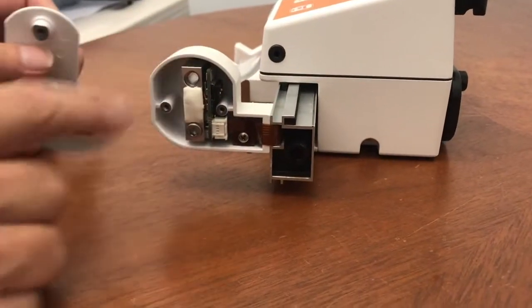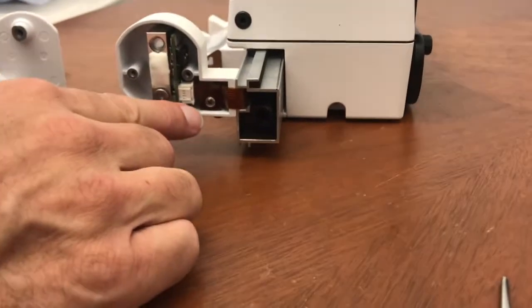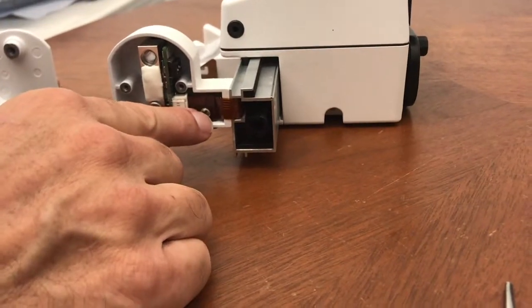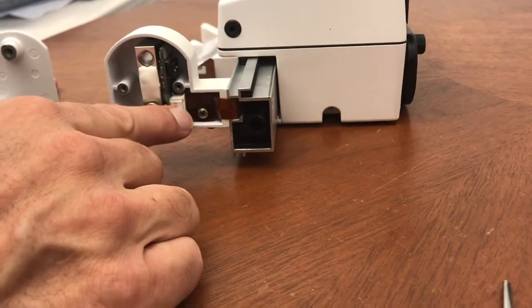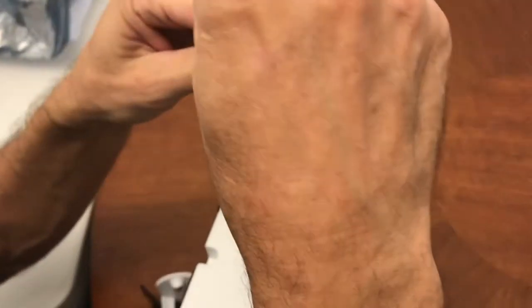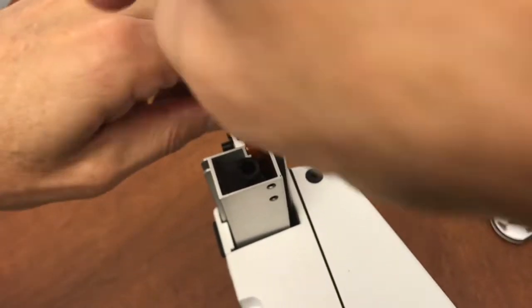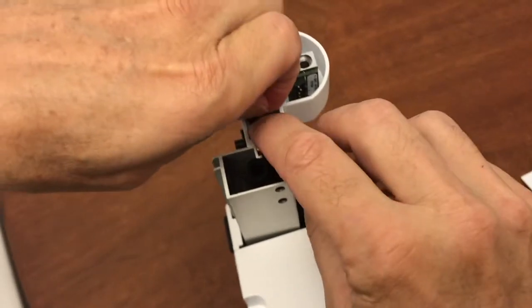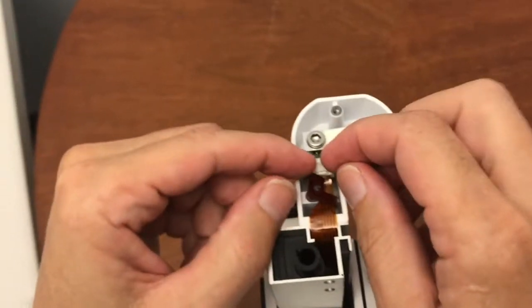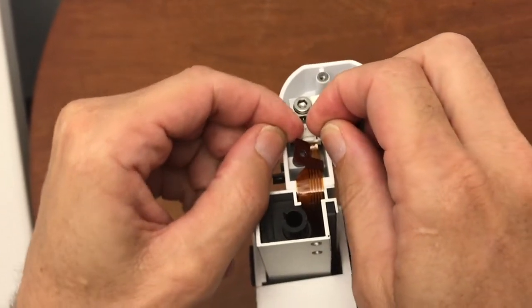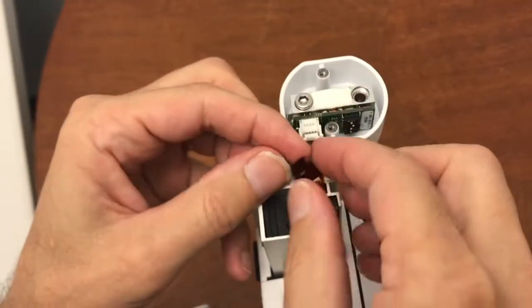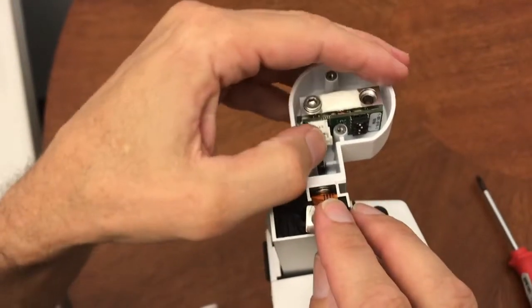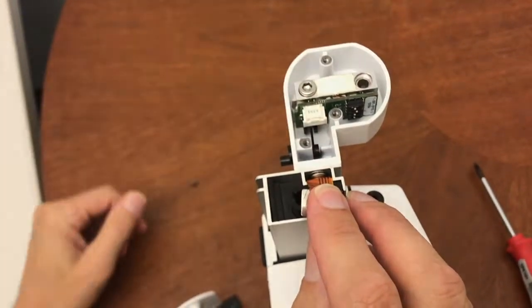When you're ready to reinstall the retainer assembly into the transducer housing, it's best and easier to remove this screw and disconnect the flex cable from this connector. Pull back on the latch, and then the cable can be disconnected. Push the latch back down.